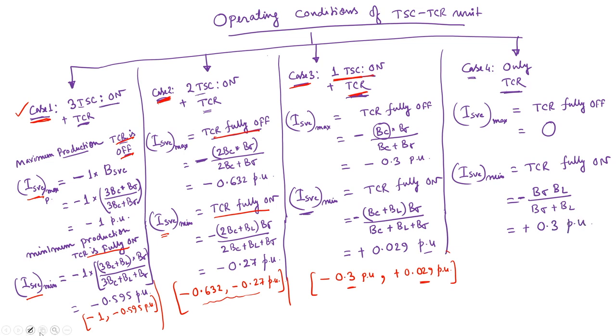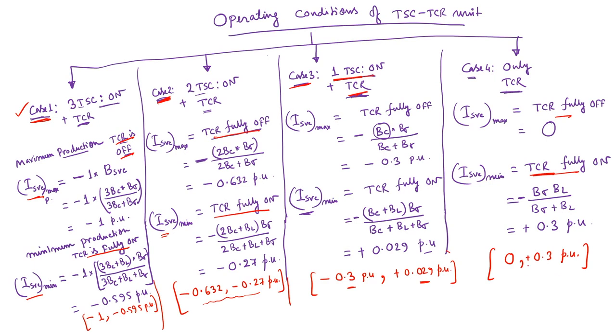So for this particular case, it is possible to vary ISVC from 0 to 0.3 per unit by varying the TCR susceptance, because for each case we consider two extreme conditions: one is TCR fully turned on, another is TCR fully turned off. But remember, TCR can also be partially turned on. So by operating it this way, we can change the susceptance of the TCR to any value between 0 and B L, providing some controllable VAR, either absorption or production.